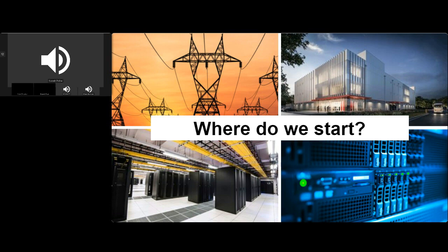And sure, you can design a distribution to be sufficient so you can convey the power into the location within the data center. But the data center is also constrained by cooling. Sometimes cooling insufficiency prevents you from utilizing power in an area where power may be available. So the problem is, it's a little complex to make sure that the amount of space you paid for, amount of power you paid for, and amount of network capacity you paid for, et cetera, exactly balance out 100% is a very difficult thing to achieve. I hope I haven't confused everybody, but it's not just the source, but how you segment the distribution, and then how you balance each segment of the distribution within the data center.